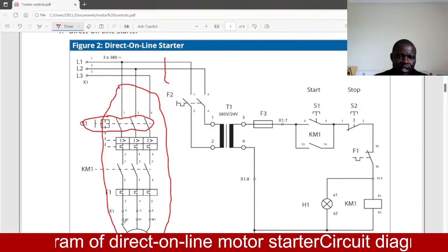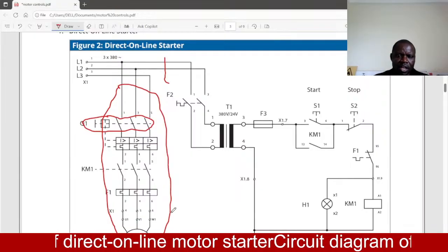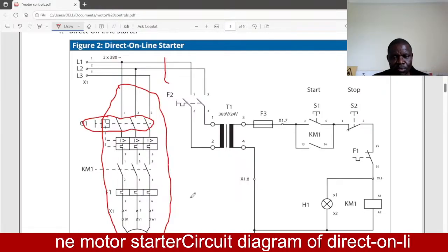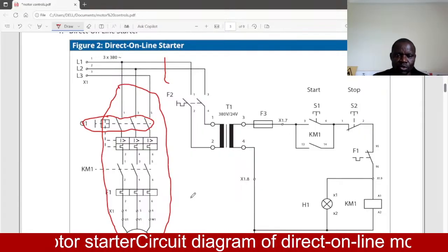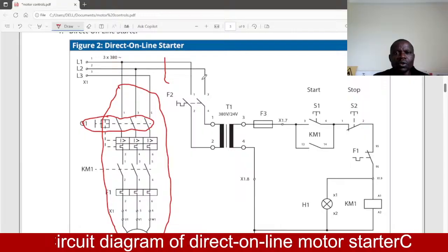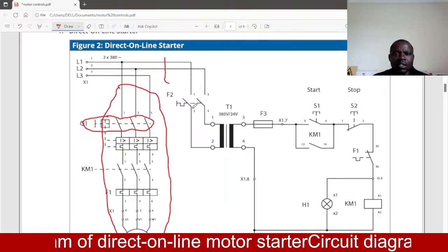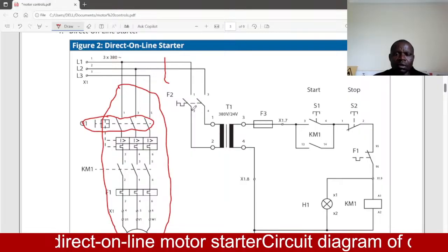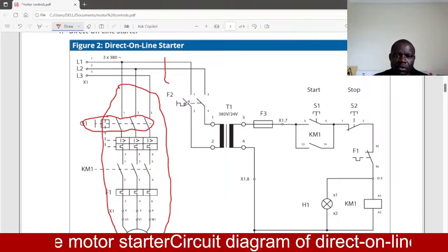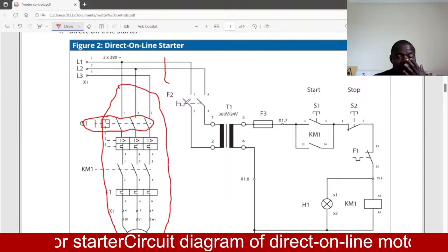When we are using direct online, we have three lines majorly coming in. And inside there, the connections may either be star or delta. Whatever the case, the terminal will bring out three terminals which are connected to line 1, line 2, and line 3. And then we have the control circuit here, which has the circuit breaker. This symbol shows that this double pole isolator has a mechanism of tripping, which is due to this coil here. This is a symbol for a coil. So in case of overcurrent, the coil will trip and it will isolate.